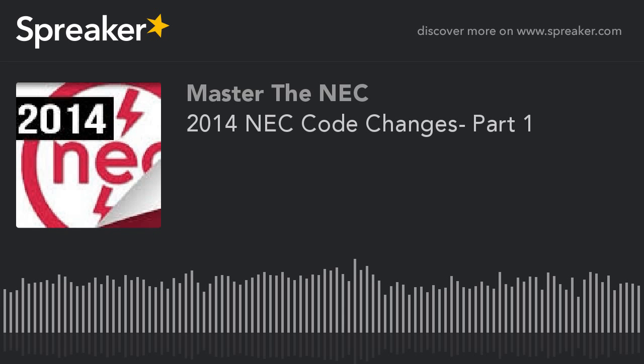The next article that gets added to this edition of the NEC is Article 728. Now, 728 is a welcome addition to the NEC, and that is called fire-resistive cables. Now, let me read you the scope, and then I'll read you what a fire-resistive cable system is, so you kind of get an understanding. But we didn't have any direction here. Manufacturers could make this product. We didn't really know its use or guidelines, and if the code called for some kind of fire-resistive cable system, what is it? If it was an emergency application system under Article 700, we just didn't know.